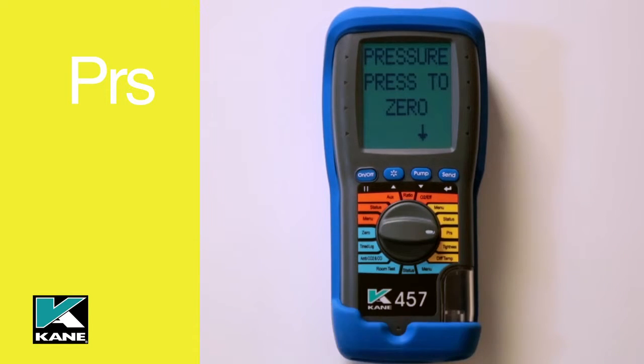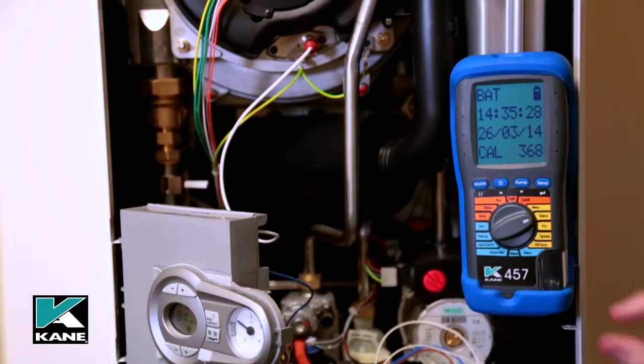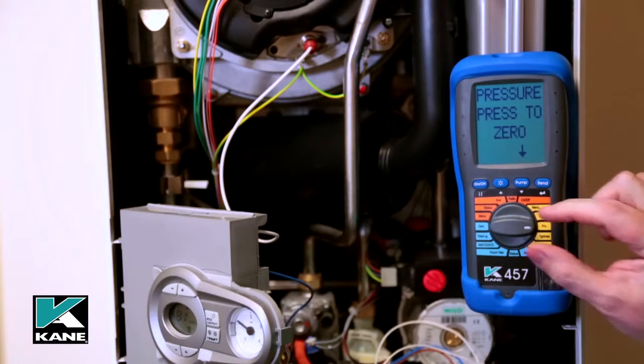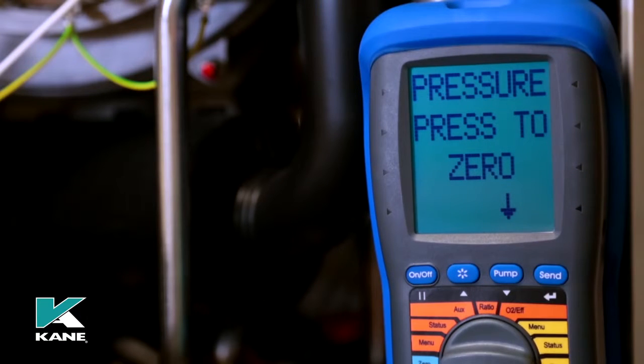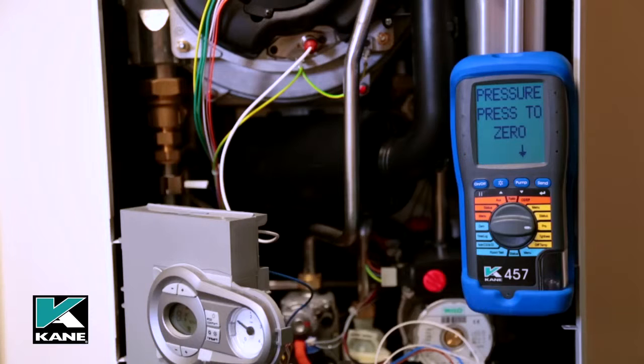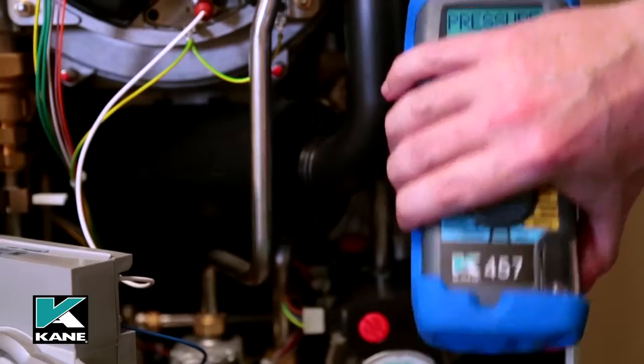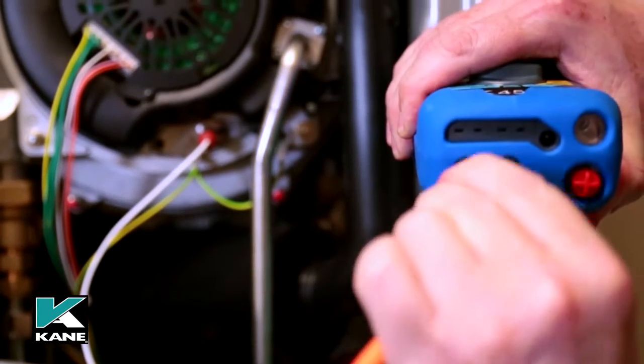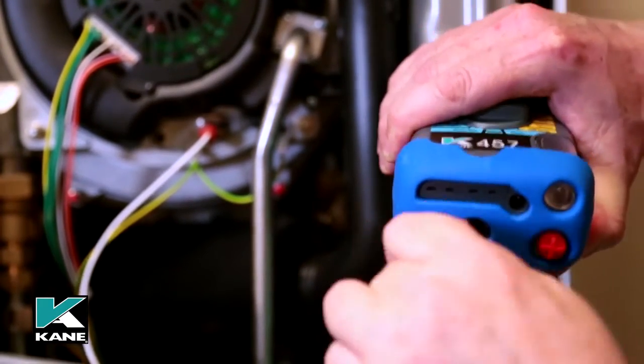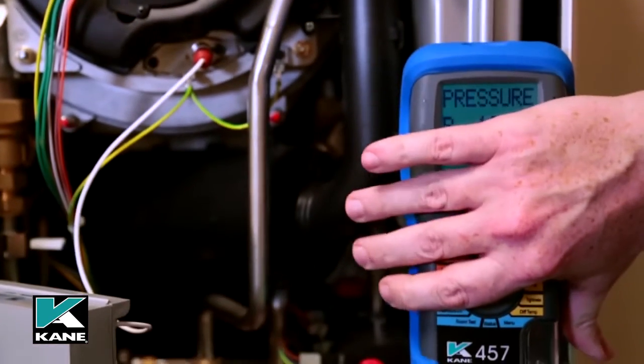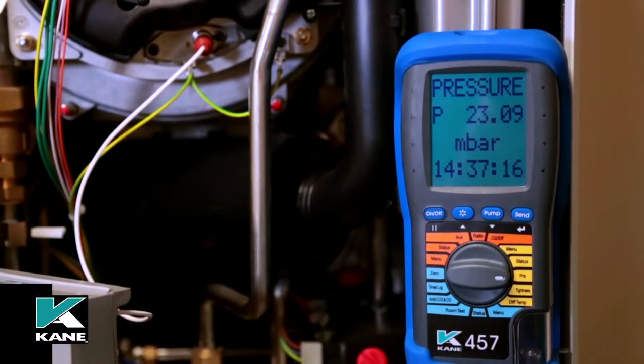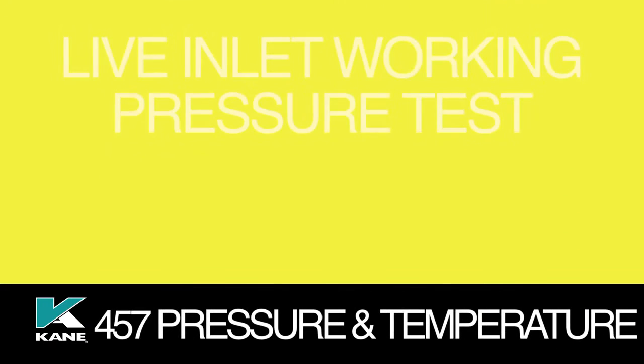Next on the dial is PRS, which is a pressure test. To carry out a pressure test, ensure the pressure hose is not connected to the analyzer and rotate the dial to PRS. By selecting PRS, the pump will stop. Press the pump button to auto-zero the pressure sensor. This ensures an accurate reading. Using the black connectors and manometer hose, connect to P1 plus or minus for single pressure, or P1 and P2 for differential pressure. We'll now carry out a live inlet working pressure test.